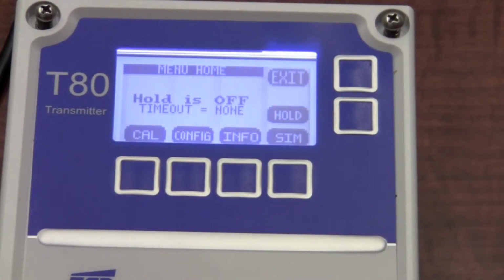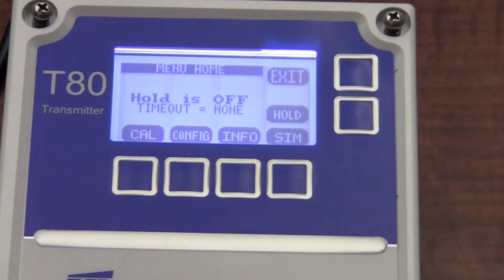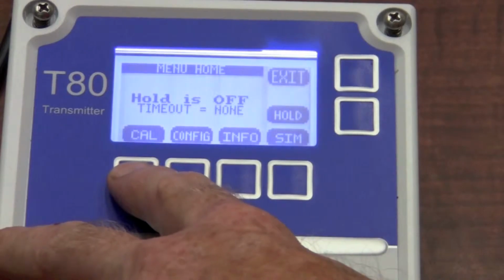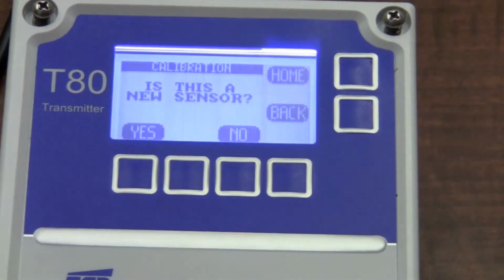After depressing the button twice, I have definitions for each of the 4 soft keys. For our intents and purposes, we're going to cover the calibration. By depressing the far left-hand key for calibration, it's going to ask me if this is a new sensor. The reason it asks this is because the T80 stores 3 calibrations. If you happen to find out that you had a bad buffer solution or something along those lines, you could always revert to one of the prior calibrations.